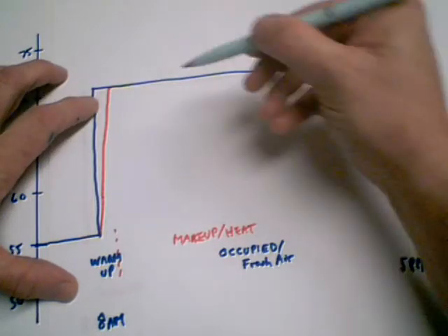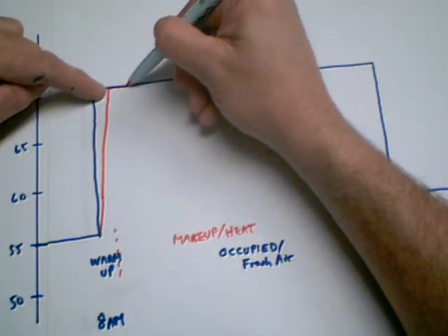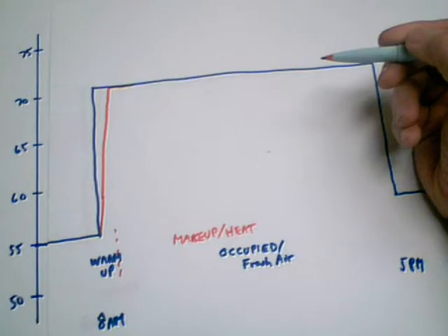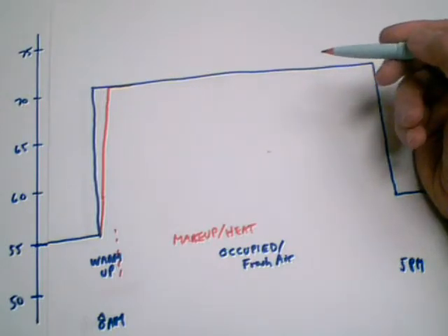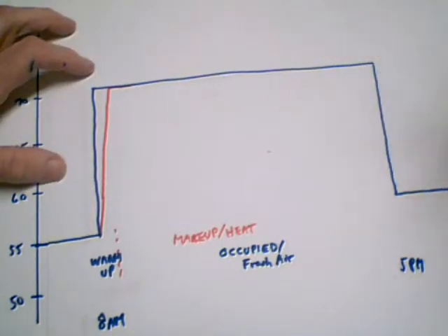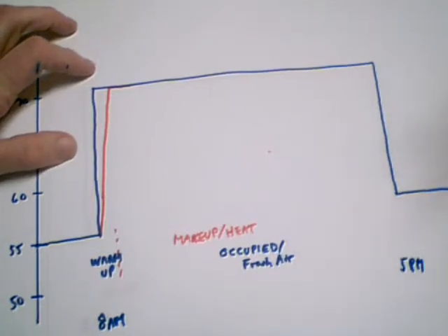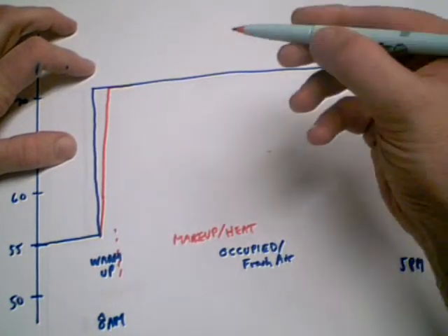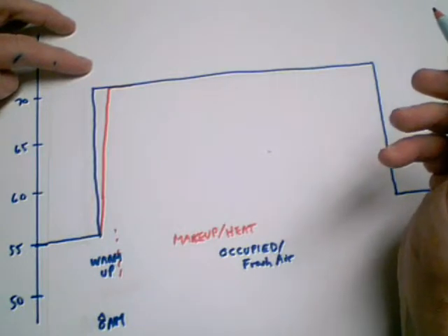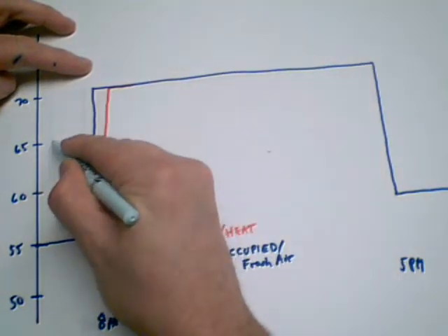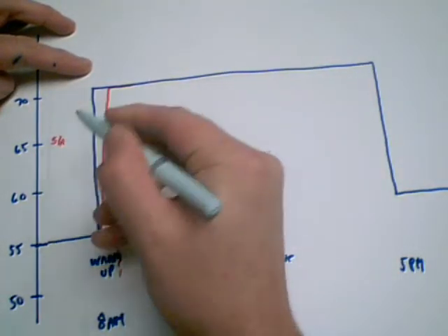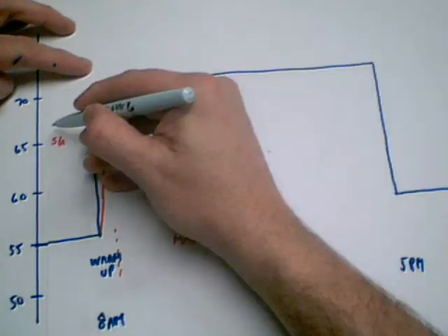So as it hits 70 degrees, it'll just go into makeup mode, which means that we're just going to turn on the outside air, so we have a ratio of outside air and return air mixed together, and that's going to be pumped through the room around and around, with the only heat content being added is just enough to bring that up so that the supply air temperature is going to be probably about 65, I think is what we said before. So this is going to be our supply air during makeup air mode.